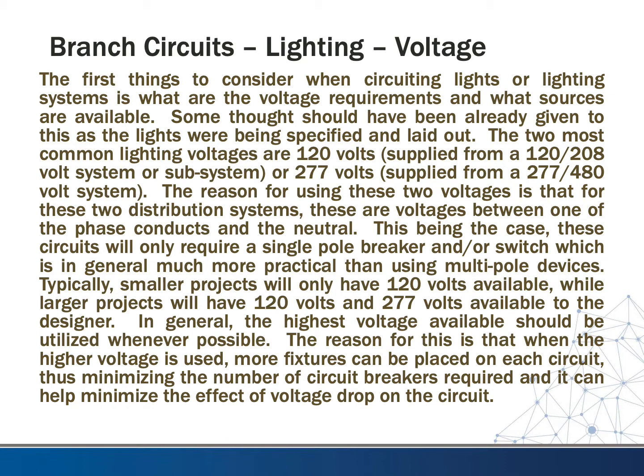The first thing to consider when circuiting lights is the voltage requirements and available sources. The two most common lighting voltages are 120 volts, typically supplied from a 120/208 system, or 277 volts, supplied from a 277/480 system. These voltages exist between one phase conductor and the neutral, meaning these circuits only require a single-pole breaker and/or switch, which is much more practical than using multiple-pole devices.